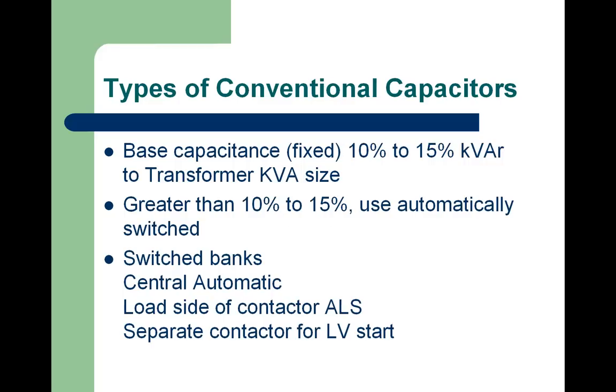Sometimes we will use a combination of a fixed bank and some automatically switched capacitors. We could even talk about the early example of putting capacitors on motors, 25 horse or 50 horsepower motors, where the capacitors would come on when the motors came on and would be turned off when the motors were turned off.